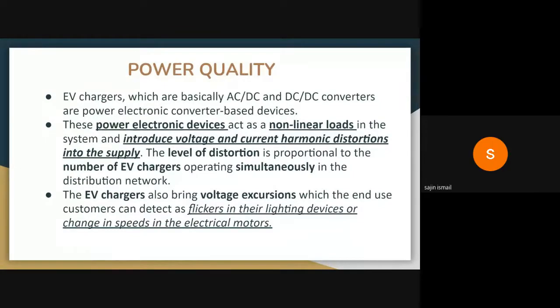From power quality - the power quality issue everybody will know is that power electronic loads are always the reason for power quality issues, because the power electronic converters, AC to DC or DC to DC converters, create harmonics and really affect the system because they are nonlinear loads. It's not just electric vehicle chargers - we already have inverters and many SMPS, a lot of nonlinear loads already in the system.